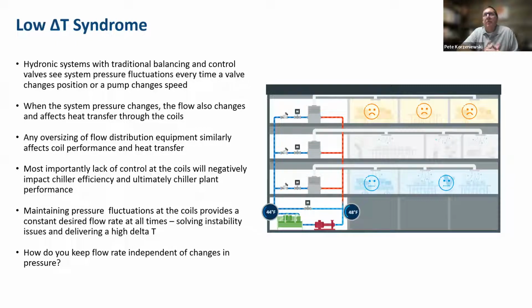If we look a little farther at low delta T syndrome, I think the audience here is going to be pretty well familiar with that. It really results from the trouble that we have with traditional balancing and control, and we have pressure situations or fluctuating pressure situations that occur in the system, and what that does to flow. Ultimately, those changes in flow that we struggle to control are going to affect heat transfer. But basically, how do we maintain that? There must be a way to balance the system. What is the best way to keep flow rate at the desired rate, independent of the different pressure fluctuations you're going to see in the building? The most common technology used for this are pressure independent control valves, or in this case, for our conversation today, we'll talk about pressure independent control devices.